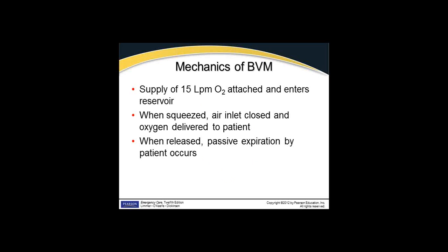So when we squeeze it, the air inlet valve closes. The oxygen is pushed out then into the patient. And when we release it, passive expiration by the patient, then we'll close the delivery valve and open the exhalation valve and blow that air out the side.